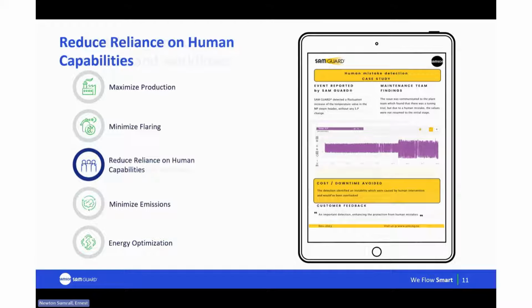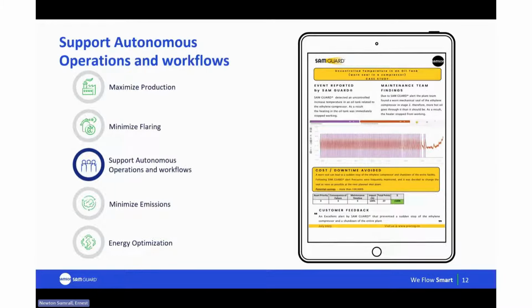In another case, SAM Guard flagged an uncontrolled temperature increase in an oil tank connected to an ethylene compressor. This triggered an automatic shutdown of the tank's heating system to prevent further issues. And thanks to the SAM Guard alert, the plant team discovered a worn mechanical seal in the second stage of the ethylene compressor, and this caused more hot oil than normal to flow through, which ultimately triggered the heater to shut down, and the cost and downtime avoided.